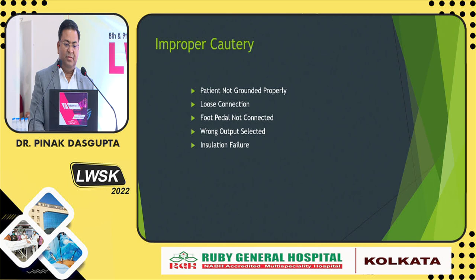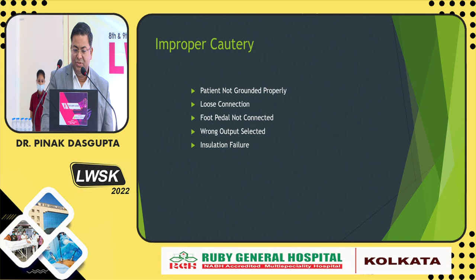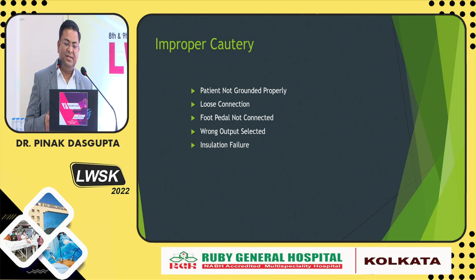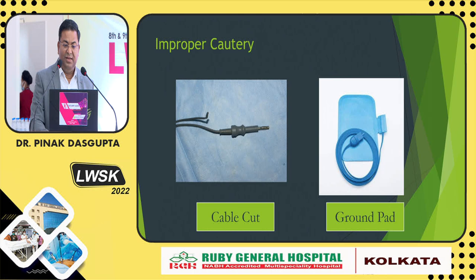For the cautery system, if it is not functional, one should ensure that it is properly grounded. Present generation cautery systems have an indicator—if not grounded, an LED light will blink; if grounded, it will be green. Check for any loose connection. The pedal has to be connected to the backside of the generator for it to work. There can be insulation failures, which may prevent proper cauterization of structures, or fracture in the cable, or a defective grounding plate.